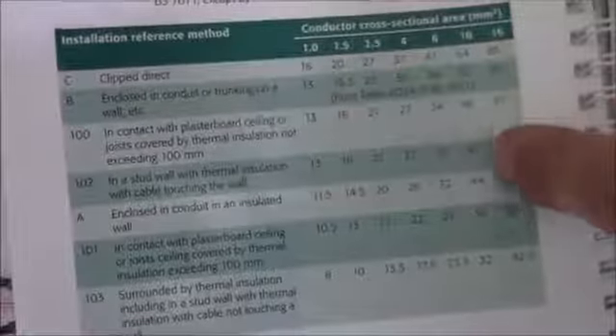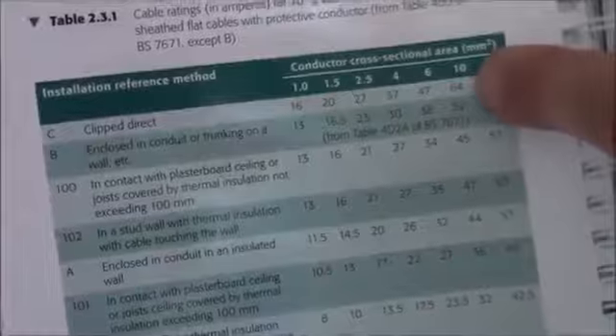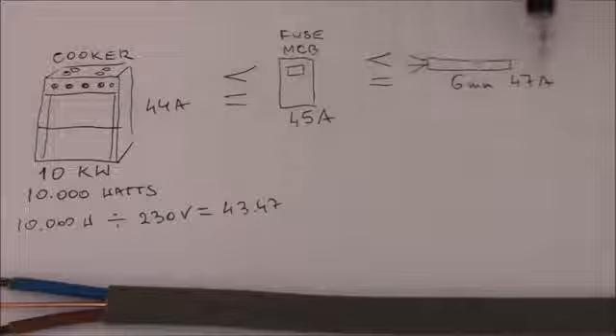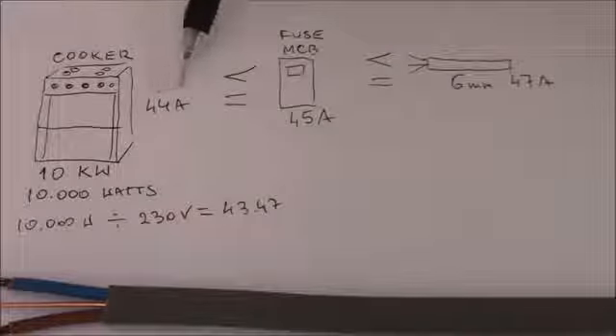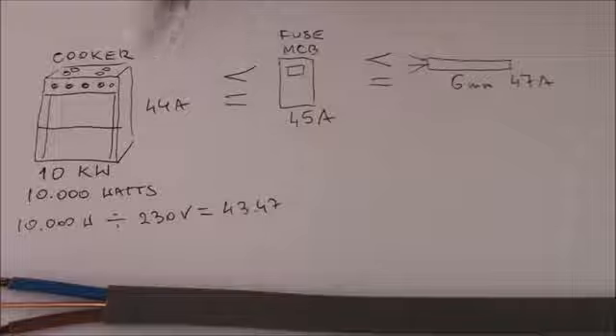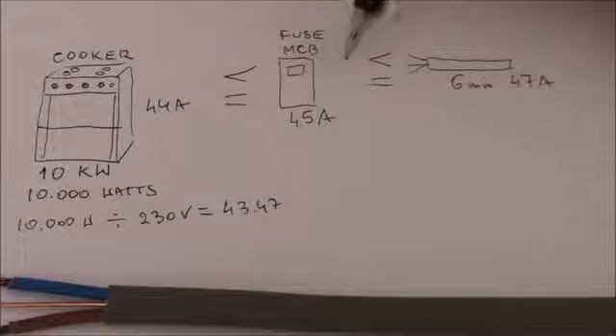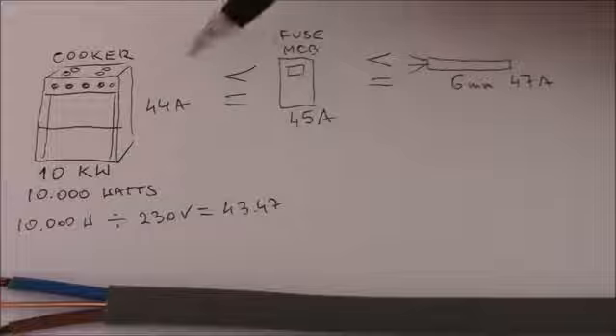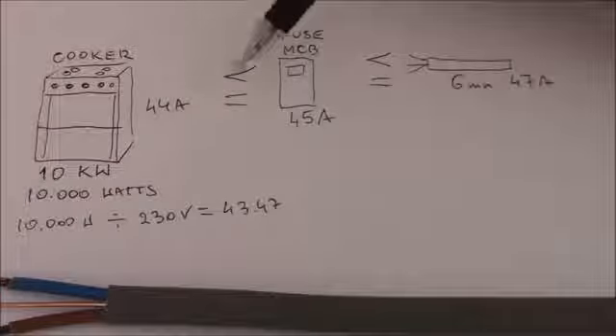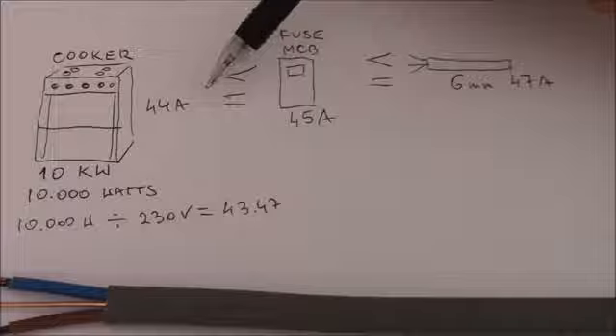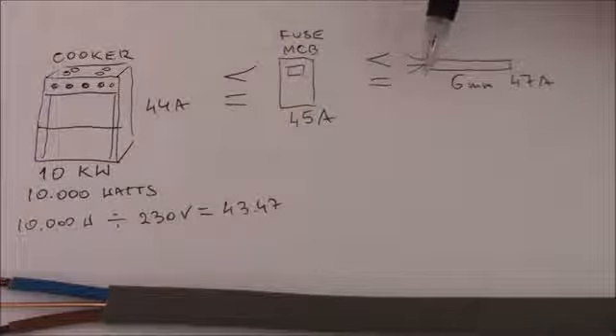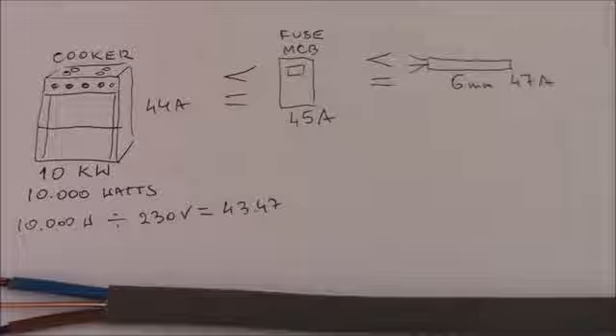So if you use the same cable and install it, for example, touching the insulation, then obviously the rating goes down quite a bit, and you have to use the 10 millimeter cable. So as you see, these numbers are just minimum. It's very close to the 44 amps that our cooker draws. So I would suggest anyway to install it with 10 mil cable, as nobody at home installs it by clipping it to the wall. So 10 mil cable would be much better.